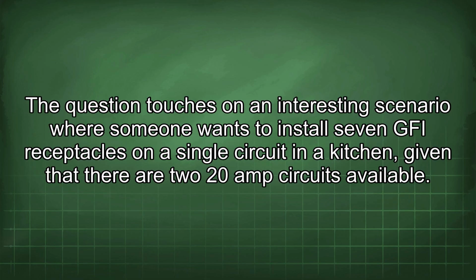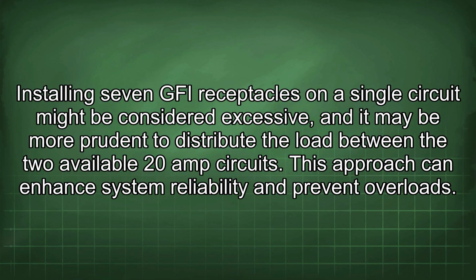The question touches on an interesting scenario where someone wants to install 7 GFI receptacles on a single circuit in a kitchen, given that there are two 20-amp circuits available. Installing 7 GFI receptacles on a single circuit might be considered excessive, and it may be more prudent to distribute the load between the two available 20-amp circuits. This approach can enhance system reliability and prevent overloads.